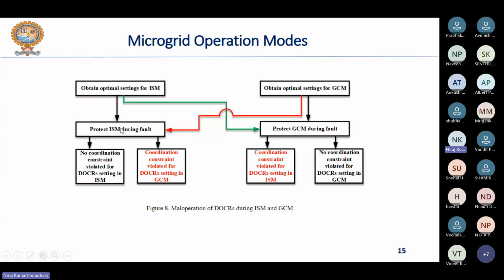So it has been observed that when the relay settings obtained in the grid connected mode of operation are tested for the relays in the islanded mode of operation of the system, then there are several constraint violations. Obviously, there will be several constraint violations because in both the cases, the fault current is different. In the grid connected mode, you have the grid present in the system along with the different distributed generators. So due to the variation in the magnitude of fault current, there will obviously be a change in the time of operation of the relay as per the IDMT characteristics of the relay that we have seen in the previous slides.